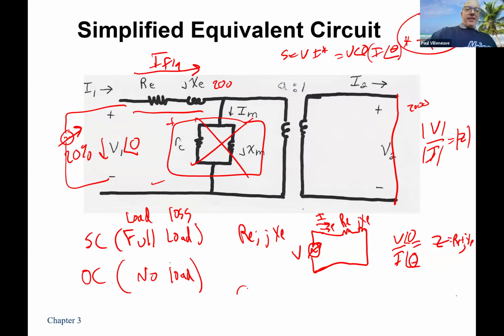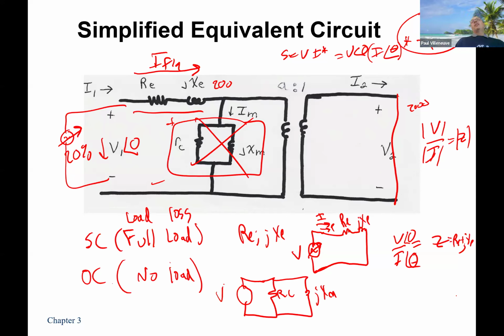So what we have is we apply a voltage. This voltage is the rated voltage of the machine because I'm trying to get what the eddy currents would be at their maximum. So usually that's at its nominal voltage. And the same thing with magnetizing. I'm trying to get as much magnetizing as I can so I can make sure my equivalent model covers all the same. So this is V rated.